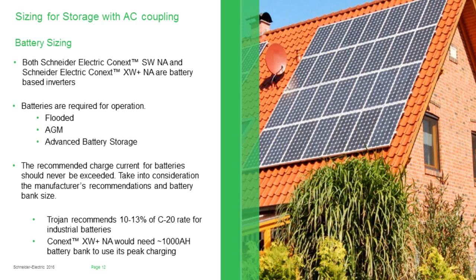There are some maximum charging amperage limits there, and you just have to make sure that you're sizing that battery bank so that we don't accidentally overcharge those batteries, or charge the batteries at too great of a rate, which, chemically speaking, is actually going to undercharge those batteries and could leave them in a partial state of charge. That really isn't the healthiest, especially for AGMs and flooded batteries. With advanced battery storage, depending on the technology, of course, it really is up to understanding what is needed for that system to properly charge those batteries. It could be that a partial state of charge is fine.